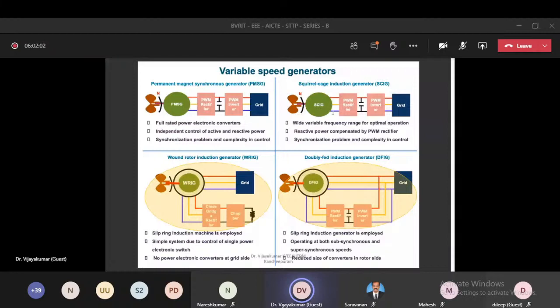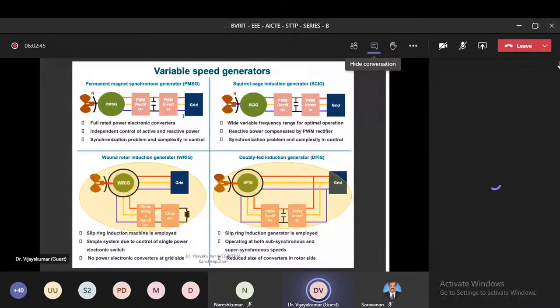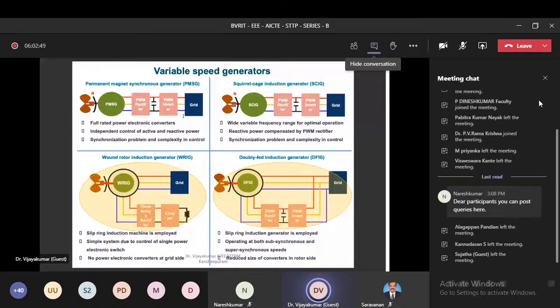So here, if you look at it, this is the basic principle of operation of this PMSG and SCIG in variable speed wind turbines. So here we will analyze this system. When we come to the analysis part, if you look at the converter ratings, these converter ratings must be equal to the machine rating, or more than the machine rating. So in this PMSG topology, this converter rating must be equal to the machine rating. Why equal to the machine rating? Whatever power is generated from this generator can be channeled through your converter to the grid, right? So your converter must be able to handle the power generated by this generator. That's why the converter rating is equal to the machine rating.